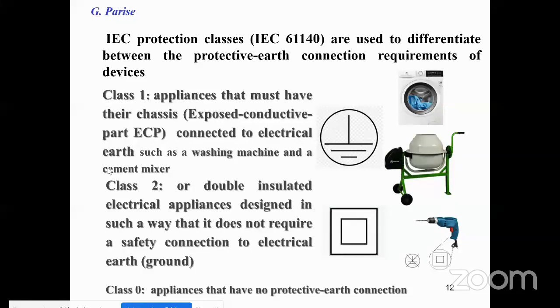Class 2 or double insulated electrical appliances are designed in such a way that they do not require a safety connection to electrical earth or ground. I have to say in this presentation, I use ground like in North America or earth like in the IEC approach. Class 0 are appliances that have no protective earth connection. This distinction between class 1 and class 2 is very important at the end of the presentation when we discuss the risk evaluation of the touch voltage.